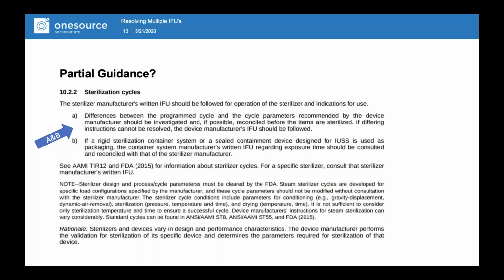So you might have to give them some more answers to get your answer. And then over here under scenario B, it talks about a rigid container system. So we're looking at a rigid container system, and that's maybe designed for IUSS as a packaging system. The container system manufacturer's written IFU regarding exposure time should be consulted and reconciled with that of the sterilizer manufacturer.